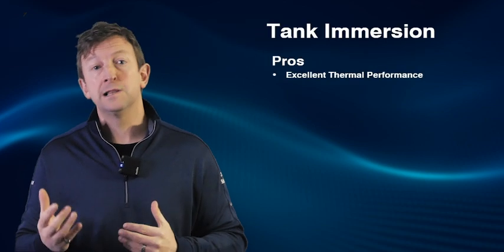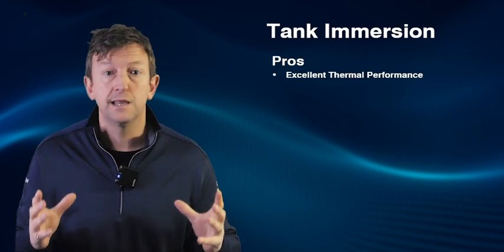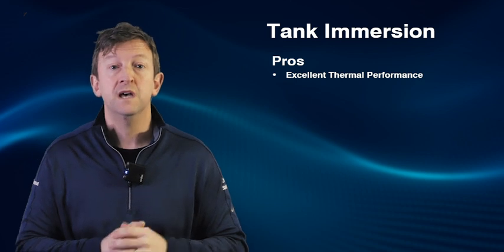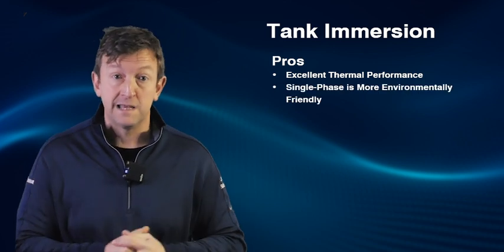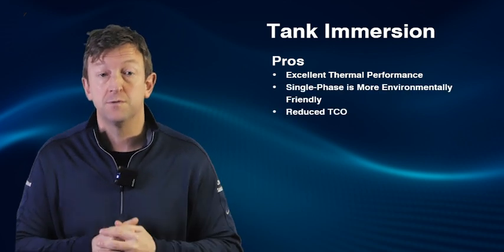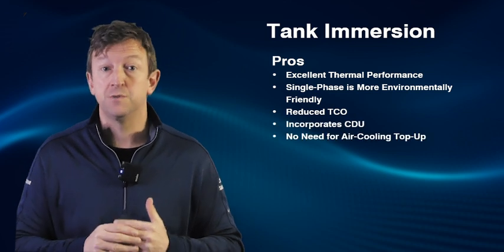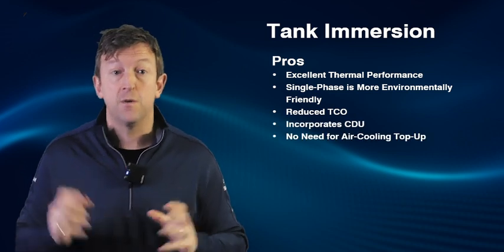Some pros of tank level immersion include removing the entire heat load with excellent thermal performance. Single phase is more environmentally friendly. You've got reduced total cost of ownership and an integrated coolant distribution unit, so there's no need for air top-up.